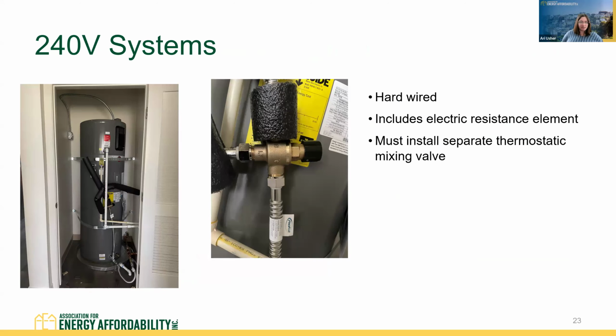So 240-volt systems, this is probably most common. These are hardwired systems. They do include an electric resistance element in the equipment. But in this case, a thermostatic mixing valve needs to be installed separately. It's not going to be incorporated into the equipment from the manufacturer.